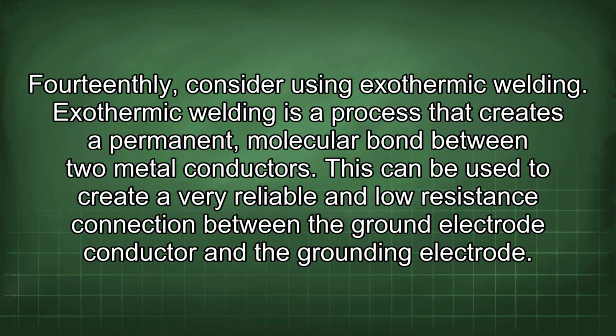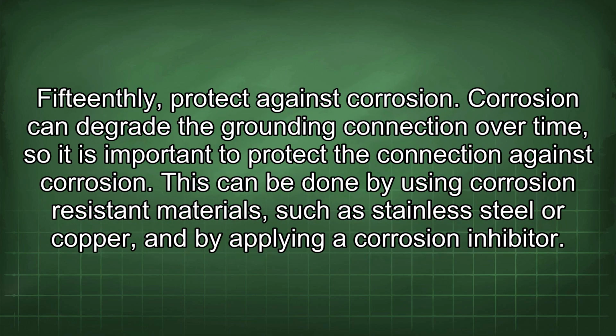14thly, consider using exothermic welding. Exothermic welding is a process that creates a permanent molecular bond between two metal conductors. This can be used to create a very reliable and low resistance connection between the ground electrode conductor and the grounding electrode. 15thly, protect against corrosion.